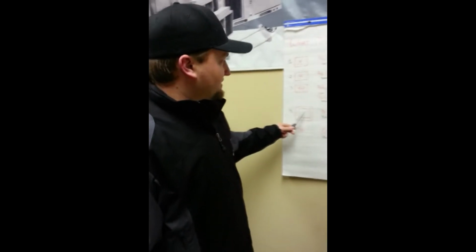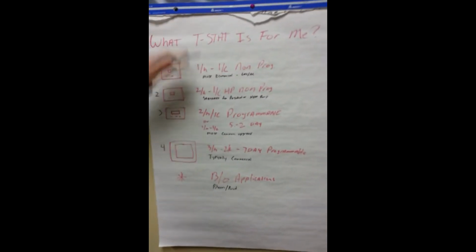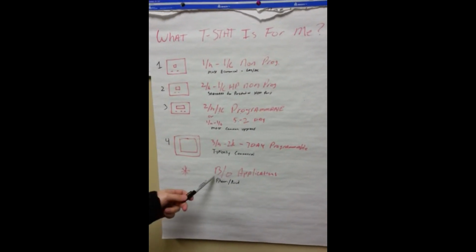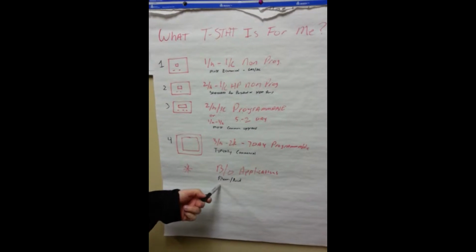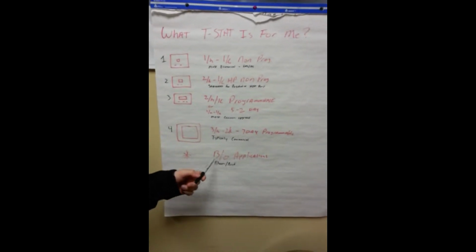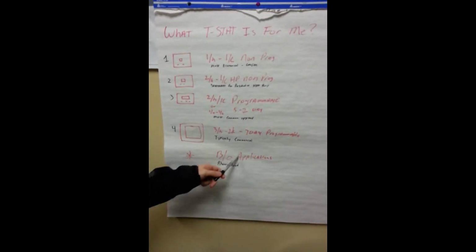Exactly. The biggest thing you have to watch with any heat pump style thermostat is what kind of heat pump do you have? What brand? 95% of them use the O terminal to shift the reversing valve, which means... Yeah, explain that, please.